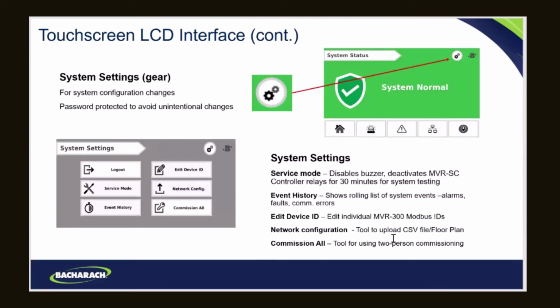The network configuration tool, this is where we have a CSV file that we include with the controller that you can use a spreadsheet to configure all the Modbus addresses and how your system is going to be laid out. And you do that on a computer, and then you can upload it into the controller. Then the controller knows the configuration of the network, and then you can use some other tools to go and commission each one of the individual gas detectors, and that's this commission tool down here. And we can work with you and get a little bit more detail around this, but it's really kind of easy to use.